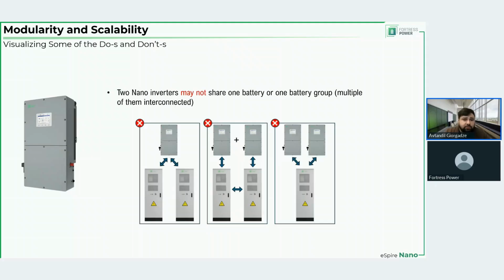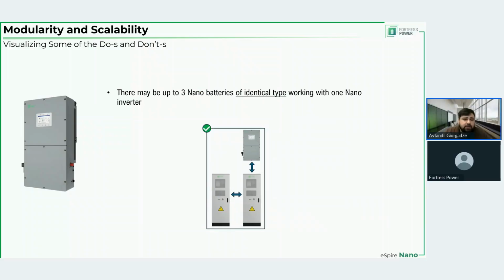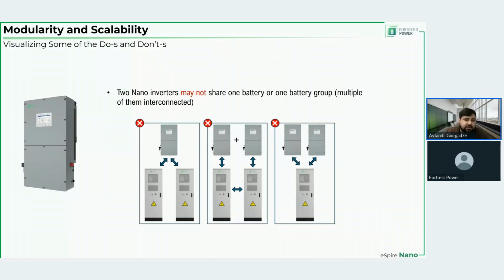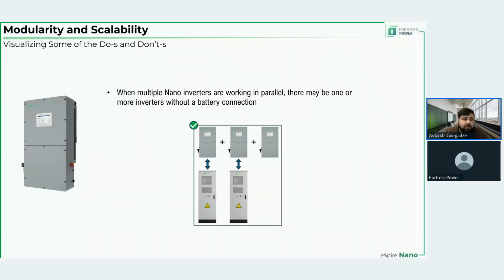One inverter sharing multiple batteries directly, instead of battery one connecting to battery two, for example, as shown here. You cannot have two batteries interconnected to one another and then interconnected one to each inverter, for example. And you cannot have two inverters working with one battery. It is okay to have some inverters working without battery, and previously I was outlining that the benefit of this is that within the same monitoring system, you have the inverter that serves as a string inverter, so you don't have two places to go to determine your total PV production, for example, right?